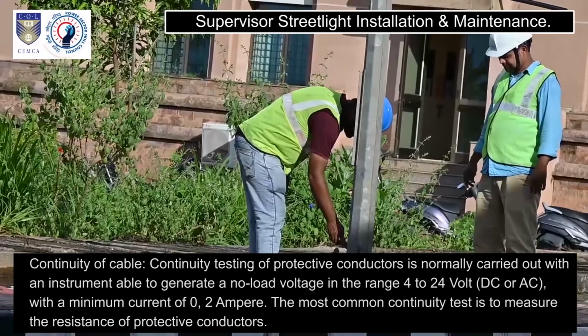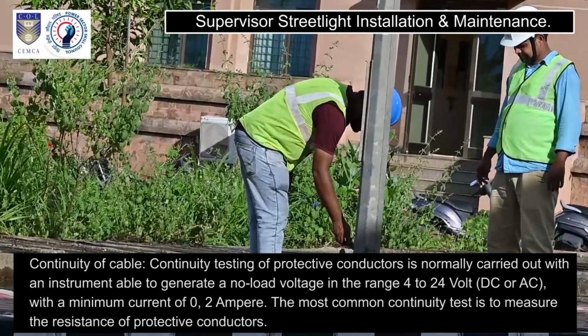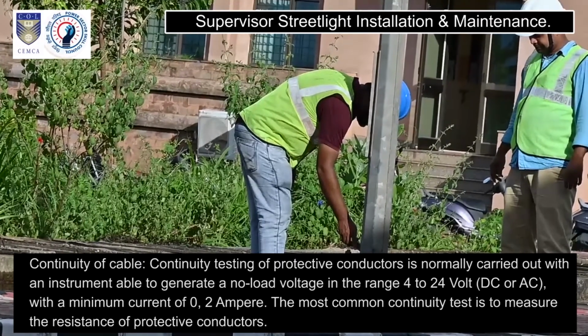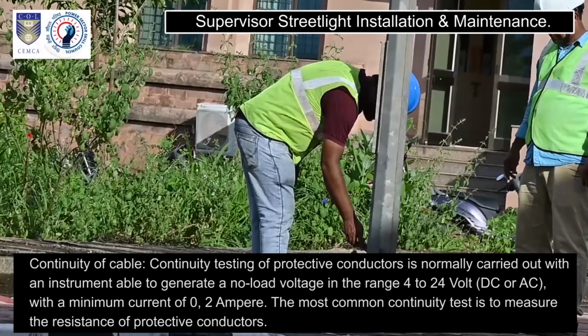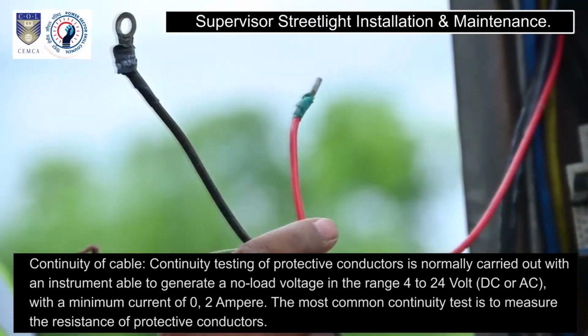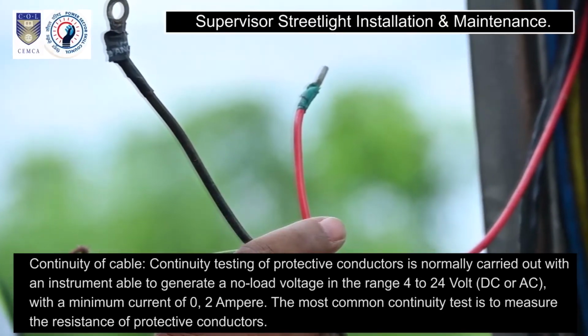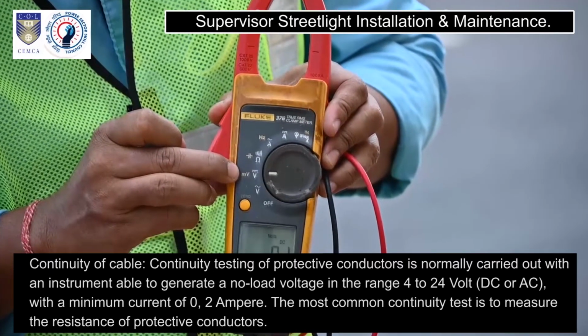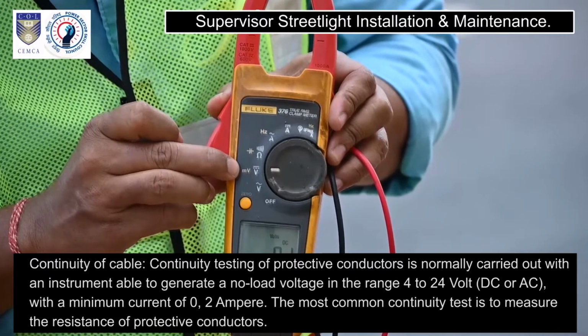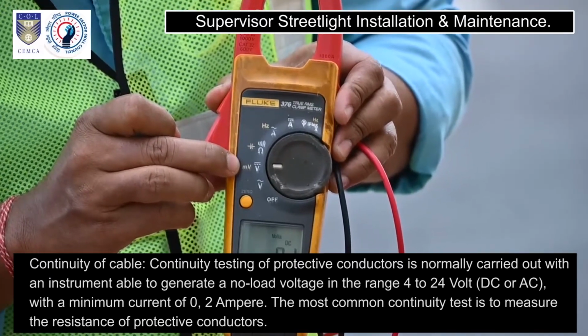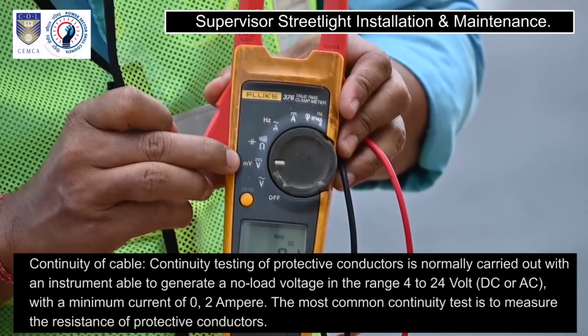Continuity of cable. Continuity testing of protective conductors is normally carried out with an instrument able to generate a no-load voltage in the range of 4 to 24 volt DC or AC with a minimum current of 0.2 ampere. The most common continuity test is to measure the resistance of protective conductors.